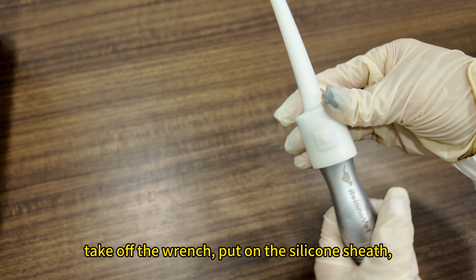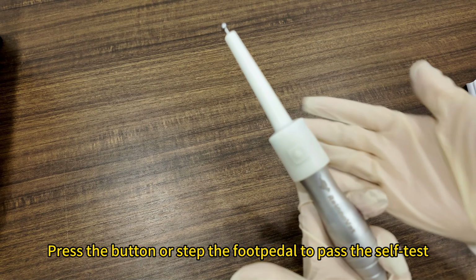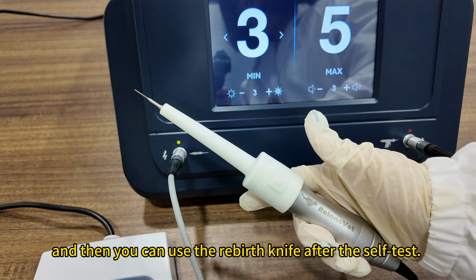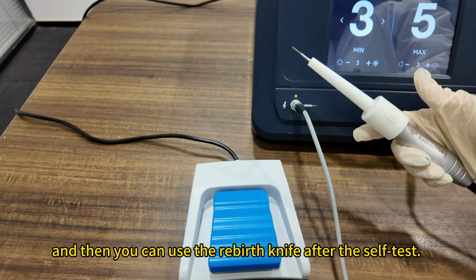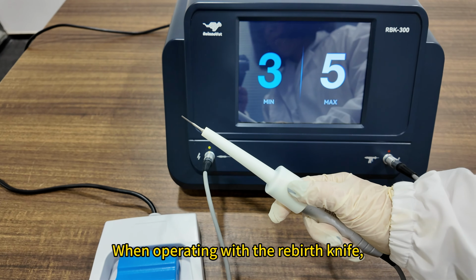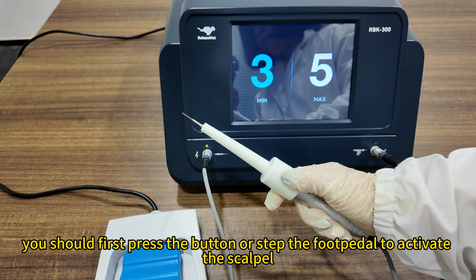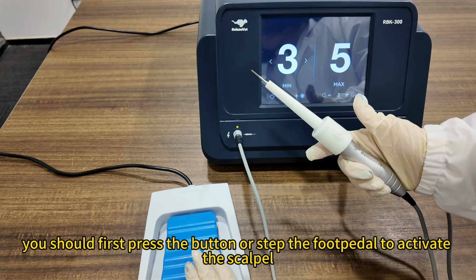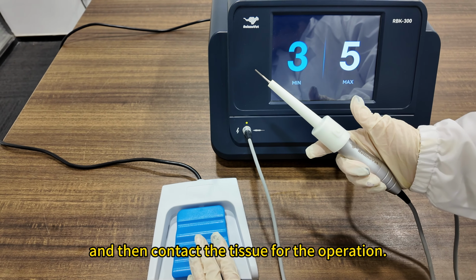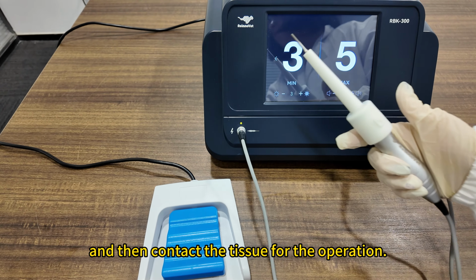When you slightly feel that you can't unscrew it, take off the wrench and put on the silicone sheath. Press the button or step on the foot pedal to pass the self-test, and then you can use the rebirth knife after the self-test. When operating with the rebirth knife, you should first press the button or step on the foot pedal to activate the scalpel, and then contact the tissue for the operation.